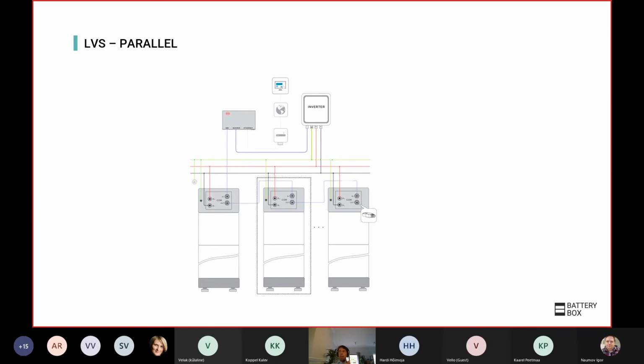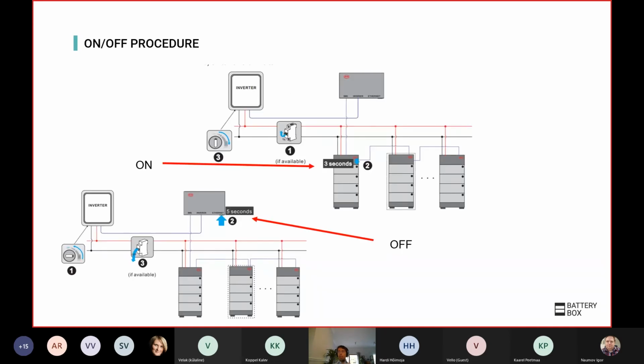Then when you put them in parallel, same as with the high voltage system, on the LVL, make sure that all the cables are identical. The only thing you need to take into consideration is that there has to be a communication cable going between the master and the different slaves. And in the last one, put the CAN terminator. The switch on procedure is the same as the LVL, meaning the inverter must be off. You just need to switch on one battery. That one battery will switch on all the batteries in the system, including the BMU. Once you have finished commissioning, you can switch on the inverter. To switch off, switch off the inverter first, and then press the BMU for 5 seconds, and this will switch off all the batteries.